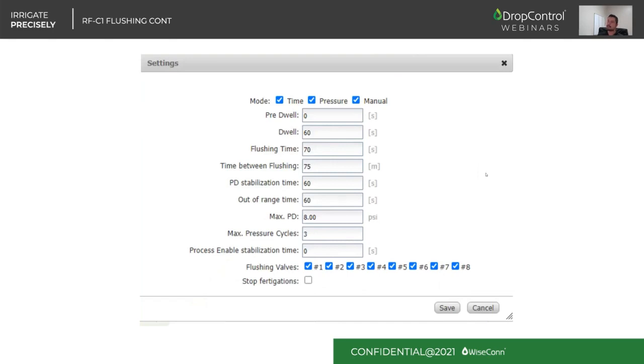As for the different settings that you are able to modify, you can select the operation mode. So you can run only by time, only by pressure, only manually, or you can have all of them enabled, or any sort of combination. So you can have only pressure and manual and disable time if you want, or you can create your own custom configuration. I'm not going to go over every single parameter, but basically you're able to control the timing of your operation: how often you want to flush, and for how long each tank or filter must be flushing. If you do have pressure readings, you can set the pressure differential that's going to trigger the flushing cycle. If you have multiple tanks, you can enable or disable which tanks will be part of the flushing cycle. And in case you are controlling the fertigation, you can decide if you want to stop fertigating or not.